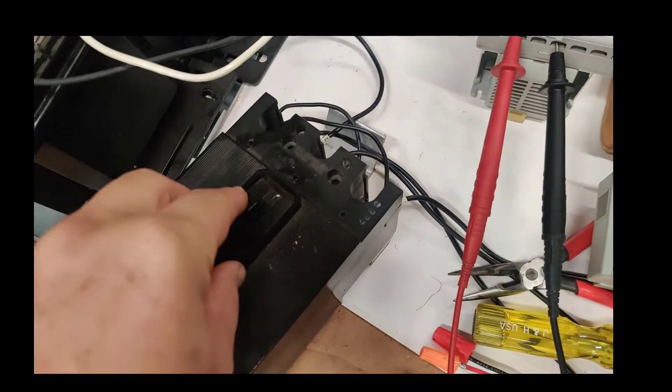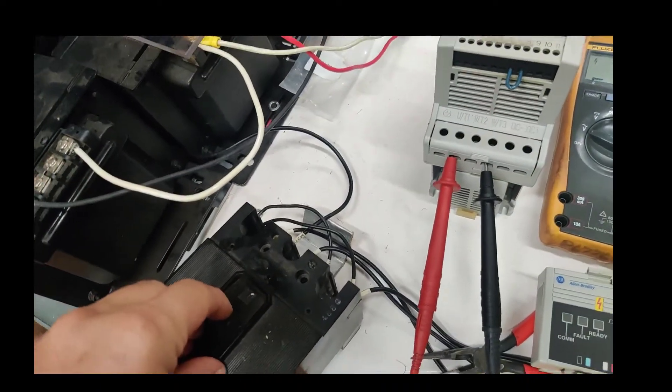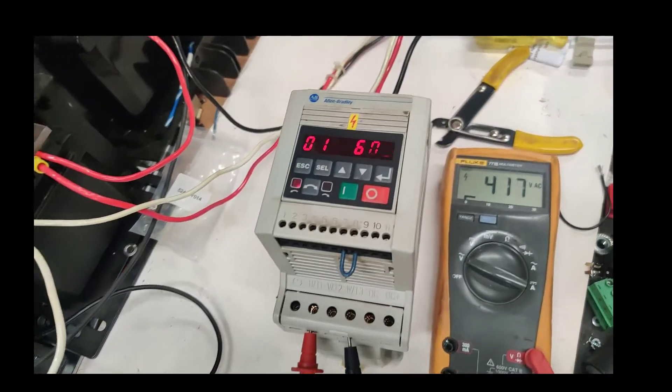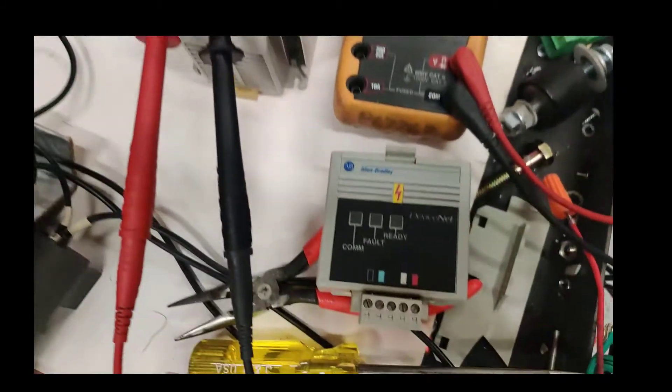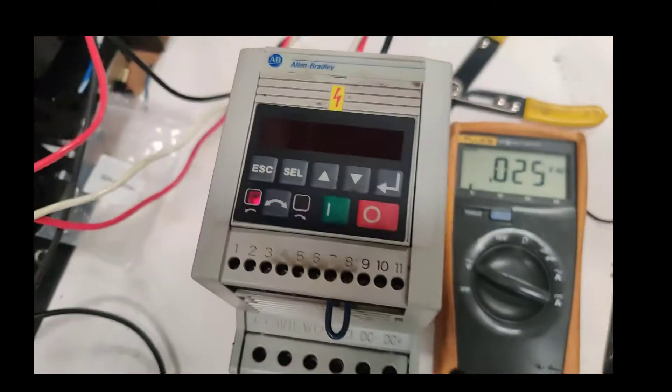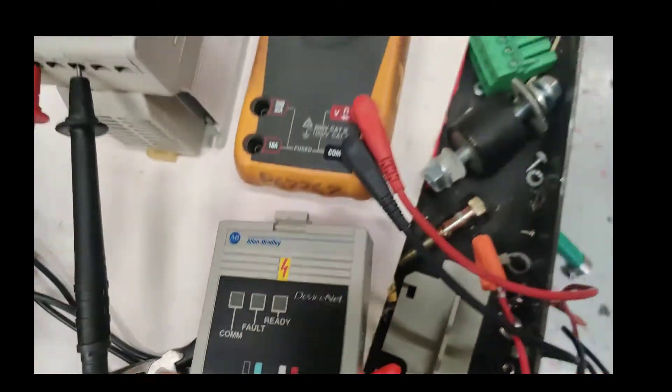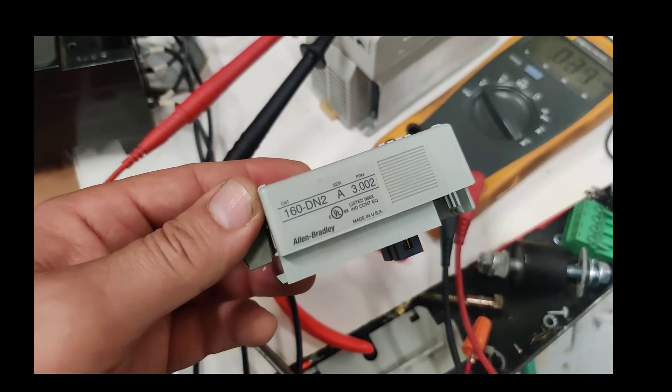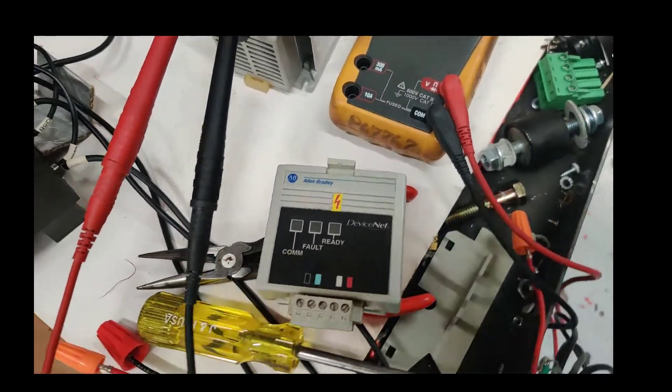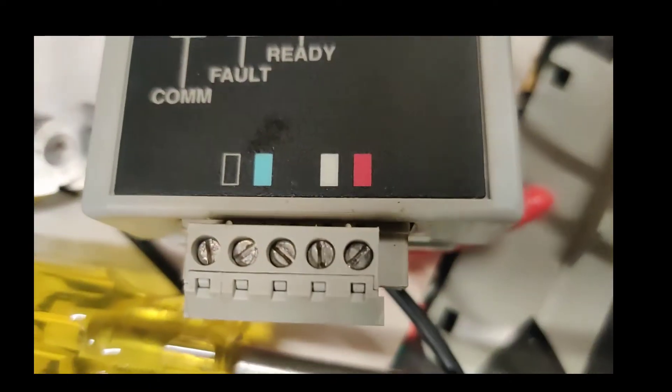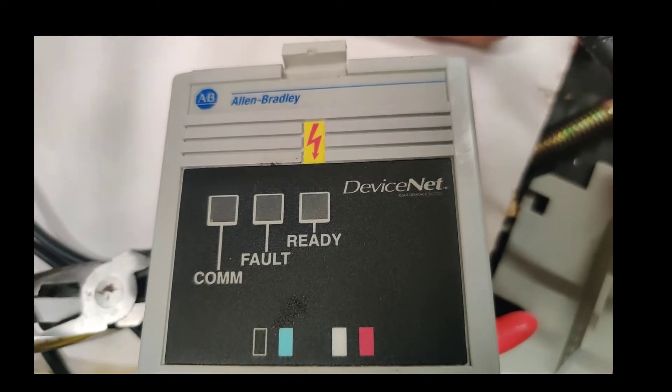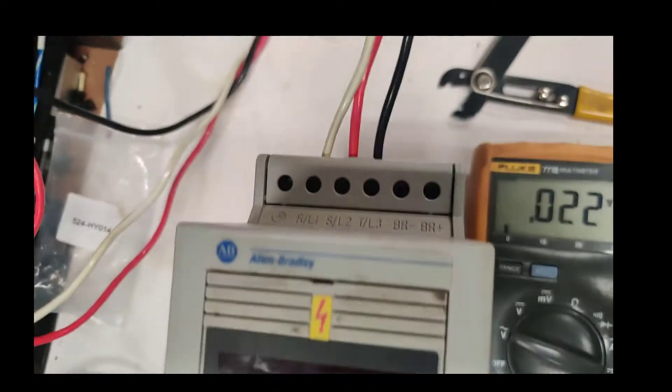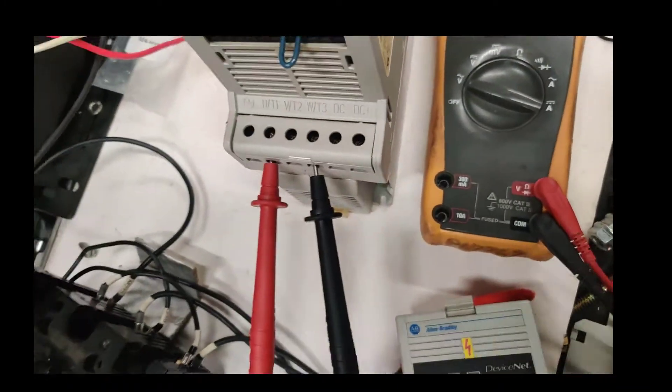You're going to see, in the test of this device, when we test this without the keyboard, just with the Device Net 160 DN2. We're going to see the fault turning on, because there is no power here. And also, the ready light, acknowledging that we have voltage right here. So let's do it.